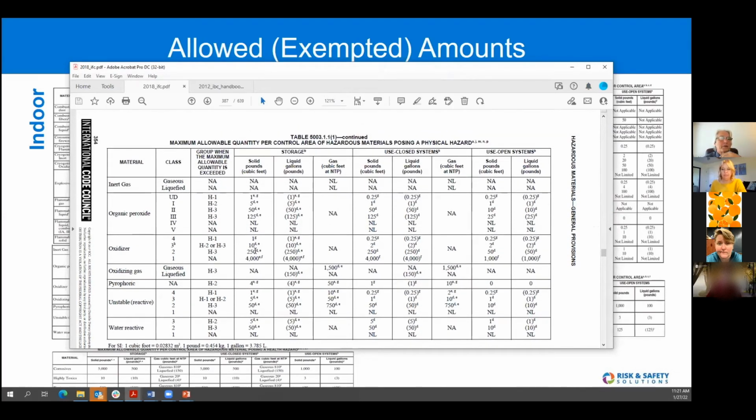a chemical inventory system can tell you what's in storage, right? It tells you what's in storage. We don't know what's in use. We have use open and use closed systems. So we can calculate the MAQ limit for an open or closed in-use system. But we don't know what you're using. You don't tell us every time you pull a bottle out of a storage cabinet and take it over to the bench to work on it. If we tracked that kind of granularity, we'd be able to give you this data, but we can generate the limits based upon the building criteria.